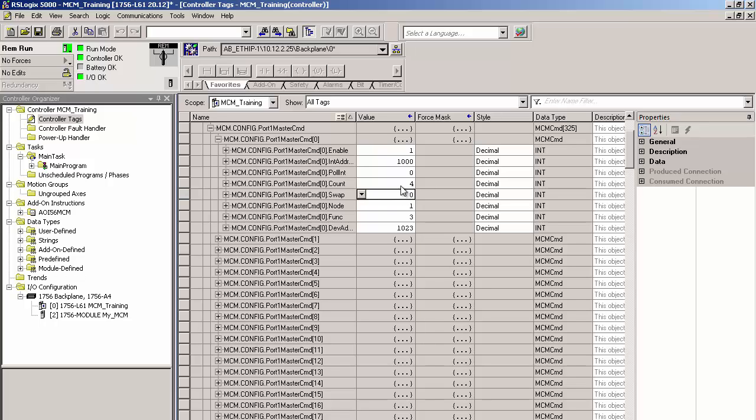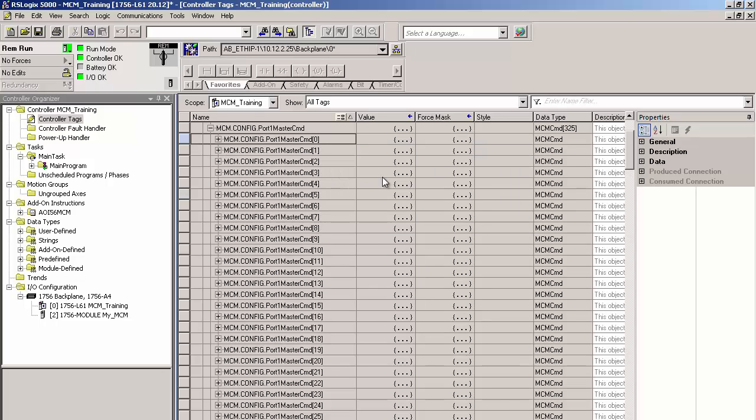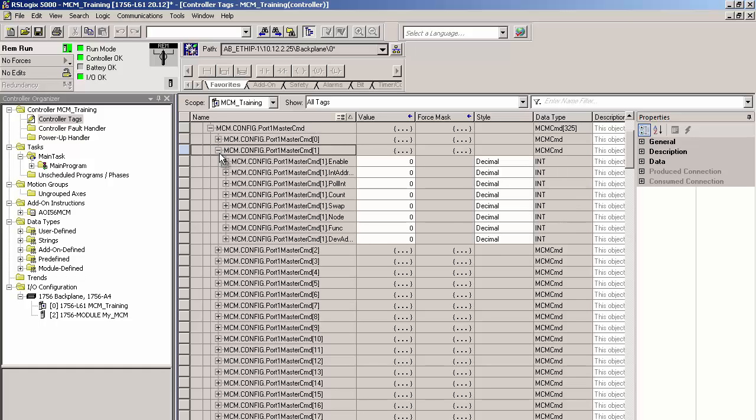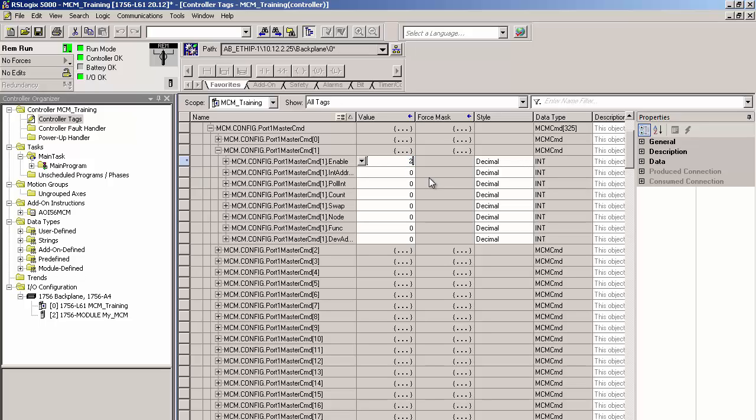Moving on, I'll create a couple of write commands. One to set the phase A voltage limit and one to reset the minimum and maximum voltage readings that we looked at earlier. I'll set the limit first. Expand MCM.config.port1 master command 1. I'll type a 2 for enable, which sets the command to execute conditionally so that it will only write if the data changes, or in this instance, if we write a new value.